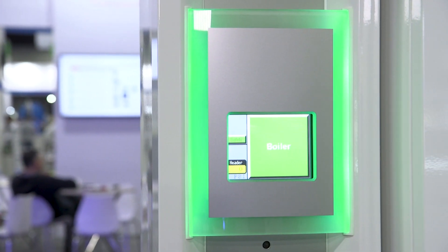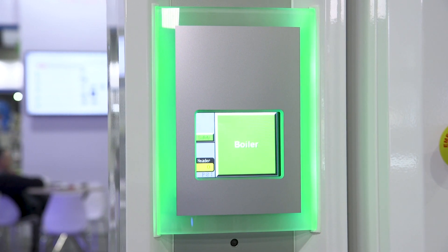One thing that sets us apart is having our BP 201 control panel. This is capable of controlling up to 36 individual boilers in an on-demand scenario. As your steam pressure demand goes up the unit will turn on boilers instantaneously, and as the demand goes down only the boilers that you need will run. Therefore you're only using the gas required to match your steam load and nothing more.